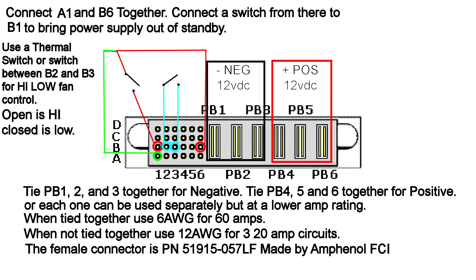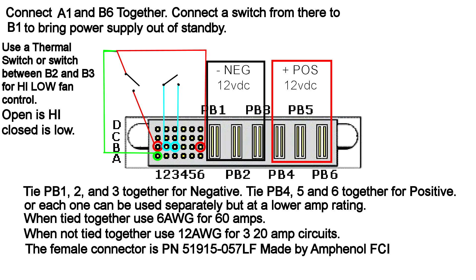This unit is always on and so if you just let it sit plugged into power it will get very warm, actually almost hot. For the fan control you take B2 and short that to B3 and in this diagram I show it as a switch that's open. Open would be high. If you're using a thermal switch, when the thermal switch heats up it opens and the fan will go to high and then when it cools off again it closes and the fan will go to low.